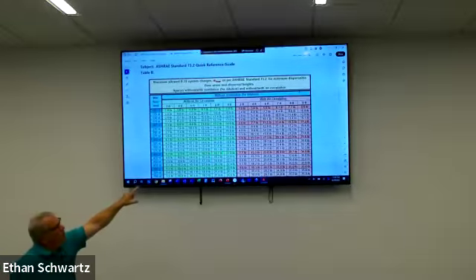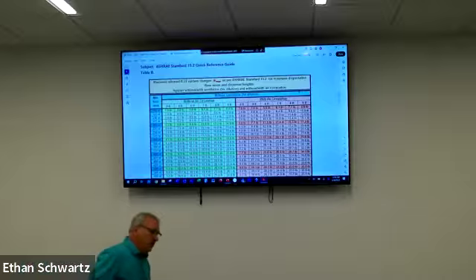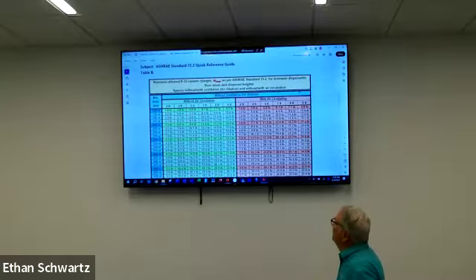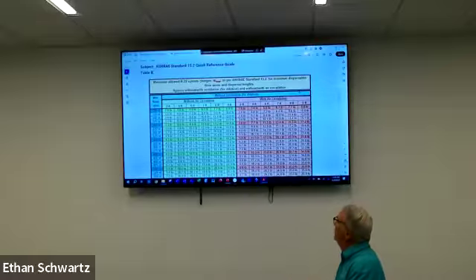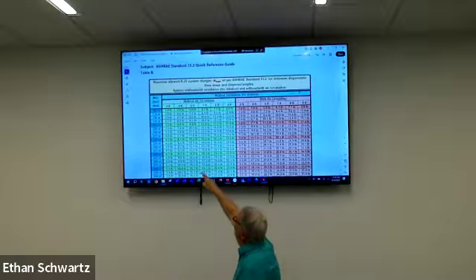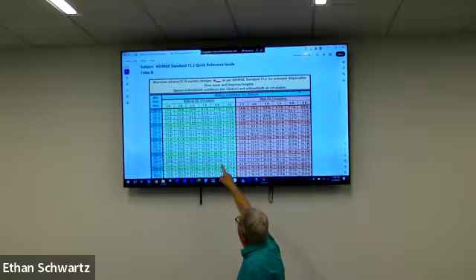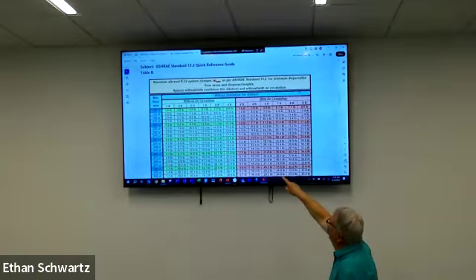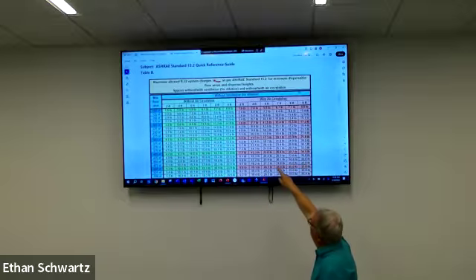So this first section of graphs is without air circulation, one is with air circulation. And air circulation is maybe there's a fan or other blower that's staying on or comes on when we have a situation that would allow air to be moving to keep that R32 from coming together. And you see if you have a minimum floor area of, let's say, a 10 by 12 room, so 125 square feet, and we're mounting a wall mounted unit at 8 feet, then without air circulation, we're good up to 9.6 pounds. That's what we look at. And then if we have air circulation, see if you come across there, it's still 9.6 pounds.